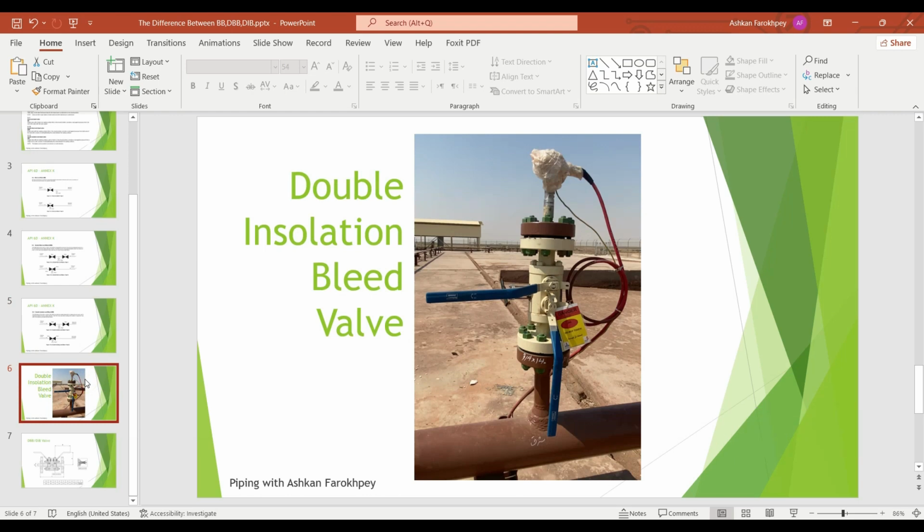Well, in this picture, we can see a DIB or DBB valve, and I titled it as a DIB because the pressure source is only from the bottom of the valve. But overall, you can see two levers, which are for the ball valves inside this unit, and a needle valve behind the lever, and its functionality, as I told you, is reducing the pressure between the two block valves or releasing a trapped fluid between them.